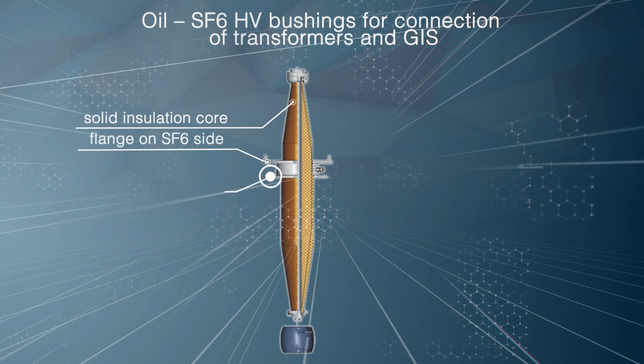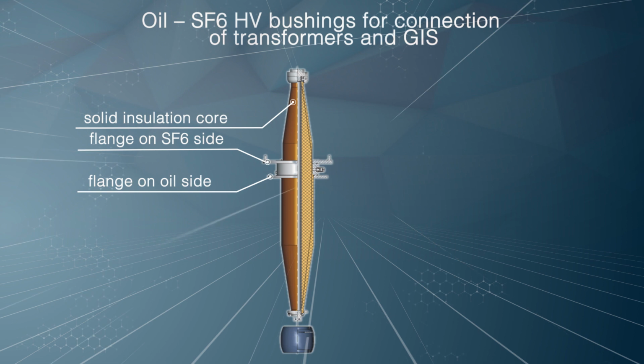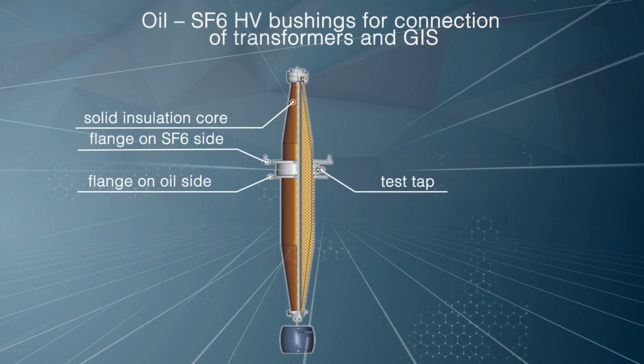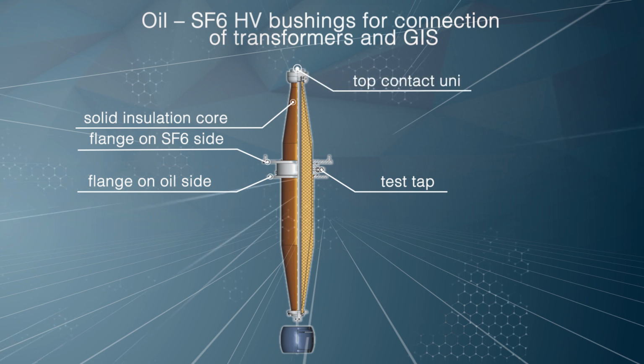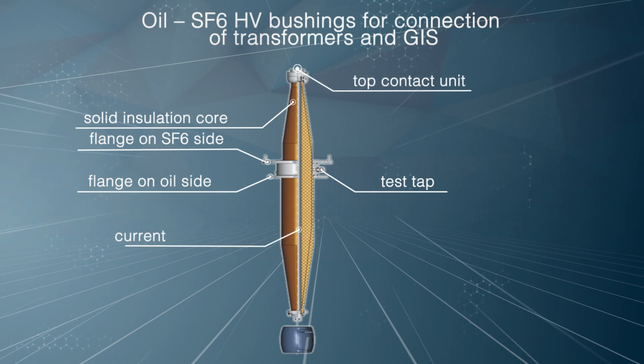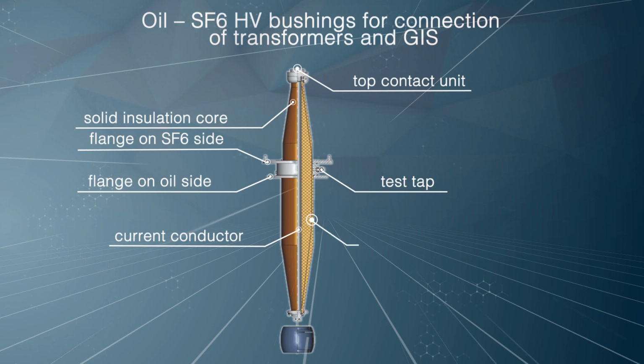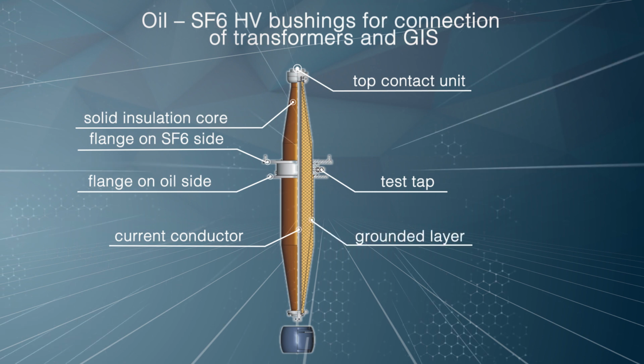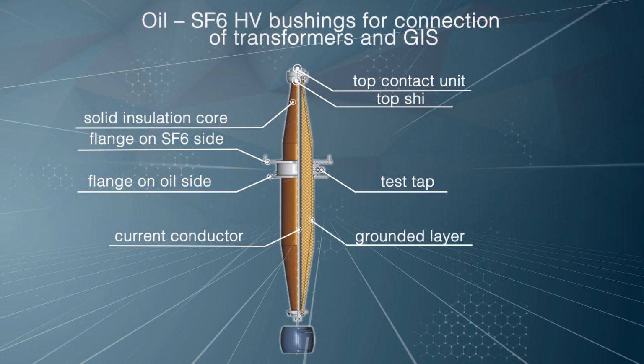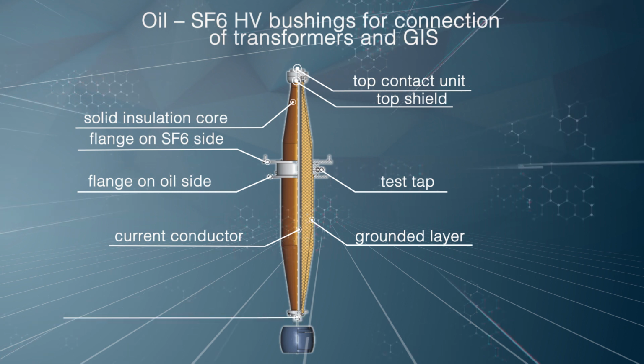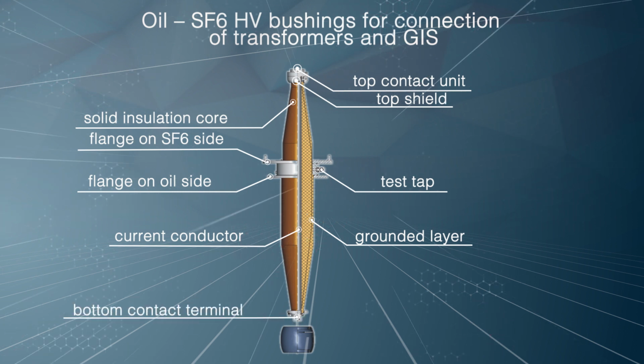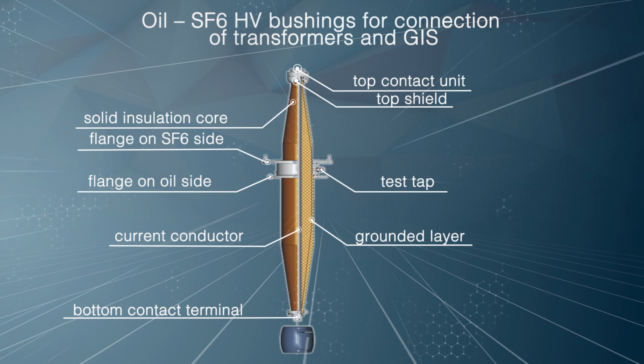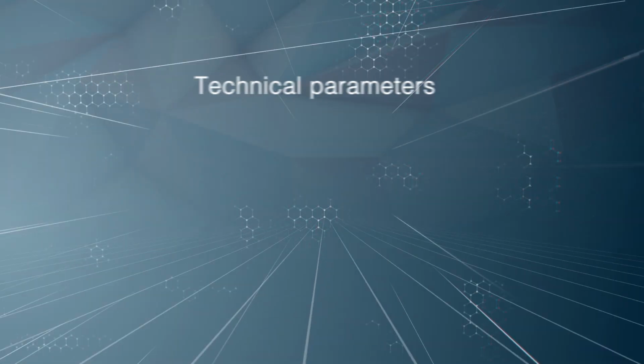In their constructional part, these bushings differ from oil-to-oil bushings by the central flange that has two mounting flanges, one for fixing the bushing on a transformer, the other, more powerful, for installing a gas-insulated contour, the top contact unit in the gas-insulated unit, the current conducting assembly rod passing through the entire tube of the bushing. It may consist of several elements.